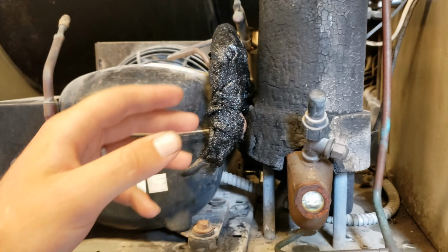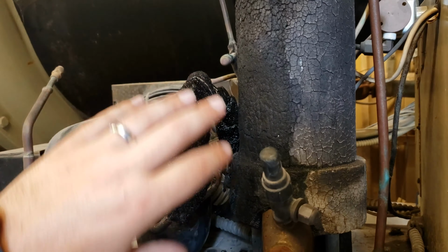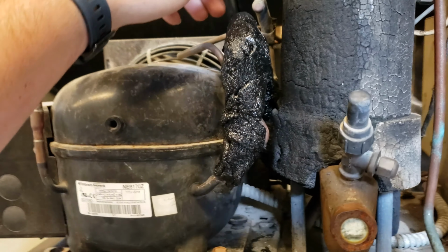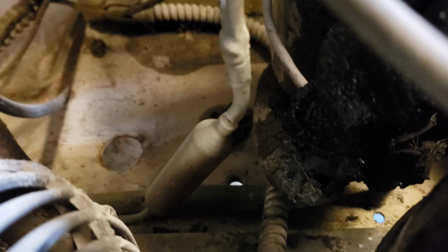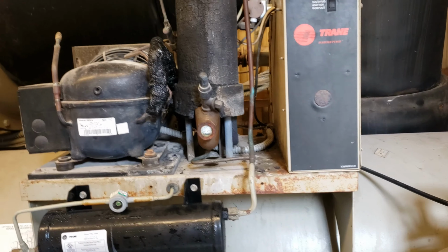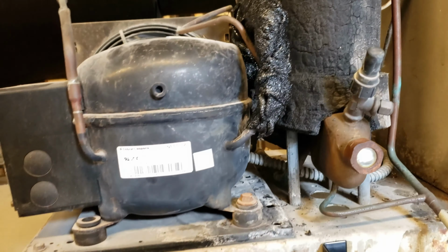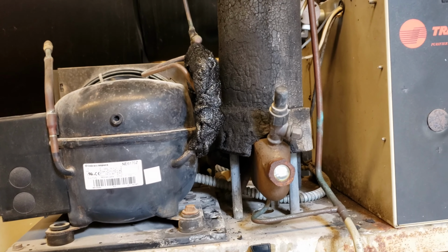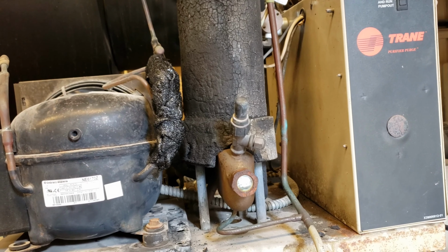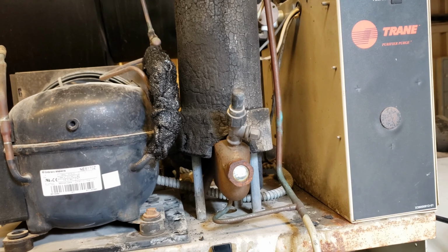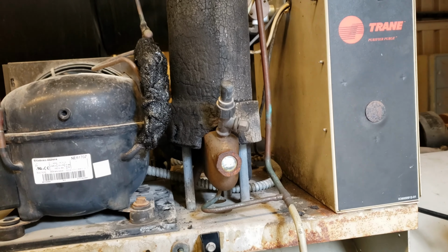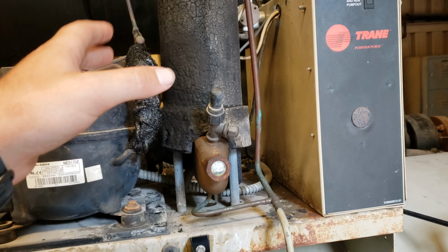but it would stay there. And sure enough, I pulled the insulation, which had a bunch of old grimy insulation on it, and on the back side, let me see if I can get a shot of it. So on the back side down there, right where that old insulation starts, there is a little threaded port that the sensor actually threads into. Well, somebody had replaced this sensor at some point in the past, and they broke the old sensor off in the threads.